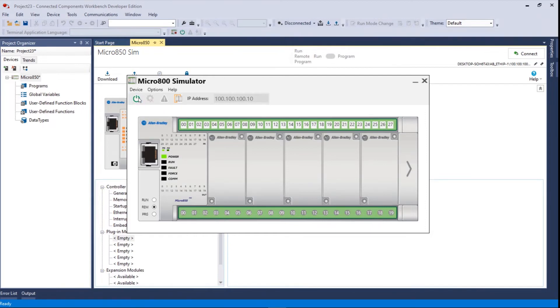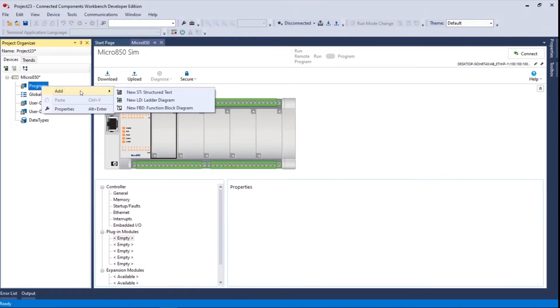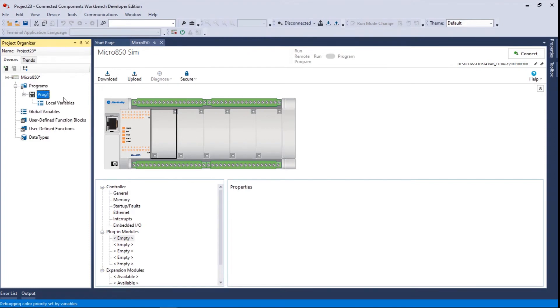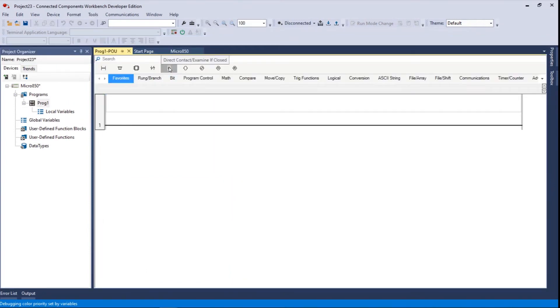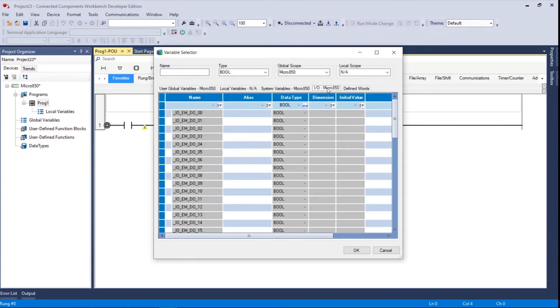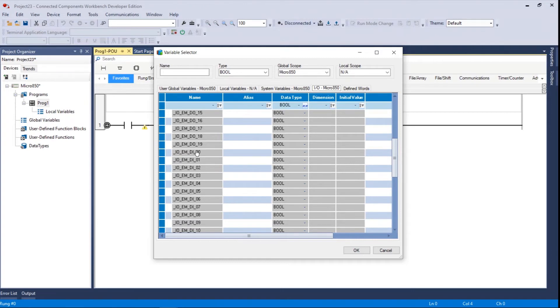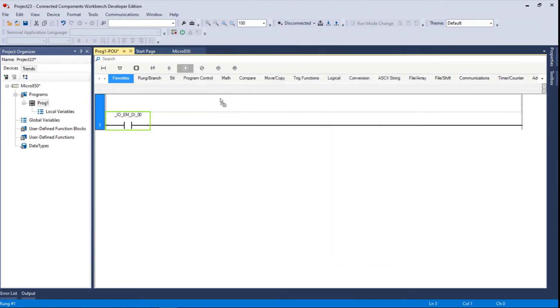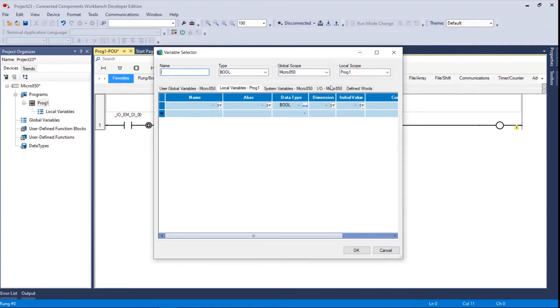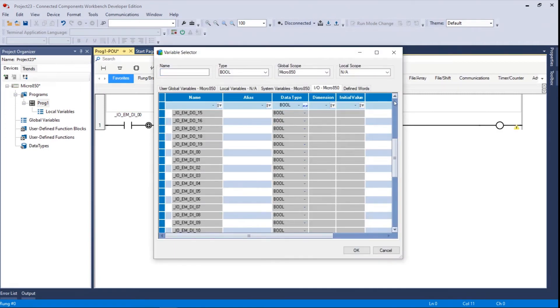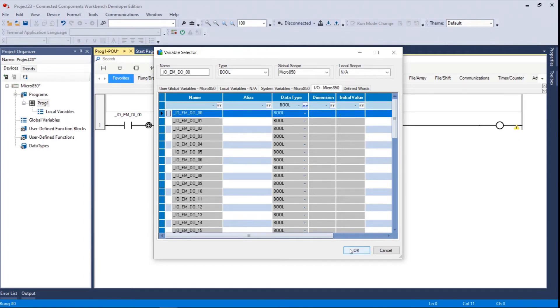It's powered up but it's not running because there's nothing in it. So now what we want to do is download something to it. Just for grins, let's create a program — a new program file, ladder logic type. Open it up and we're going to put in one rung of logic. Grab a normally-open contact and assign a variable. Go to IO for the Micro 850 and pick digital input zero.